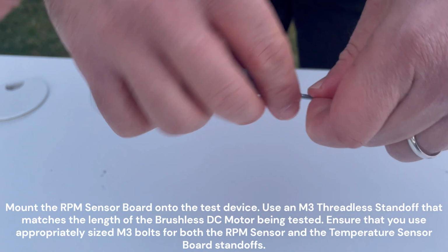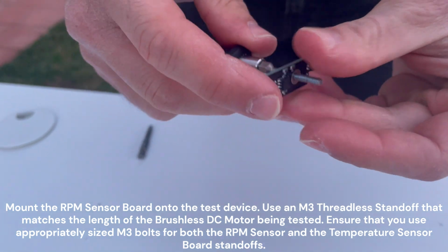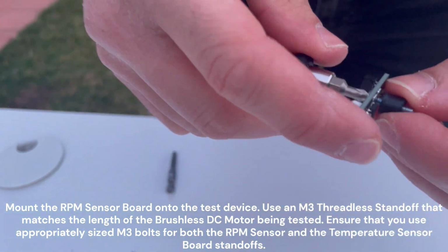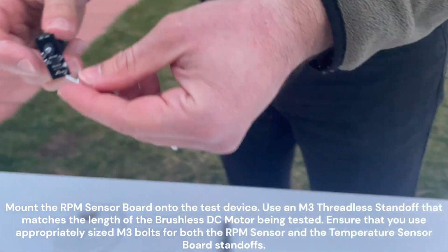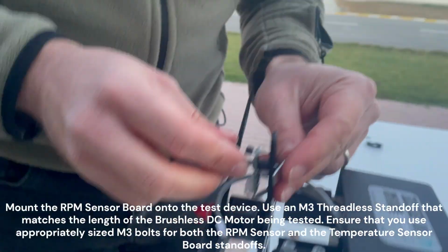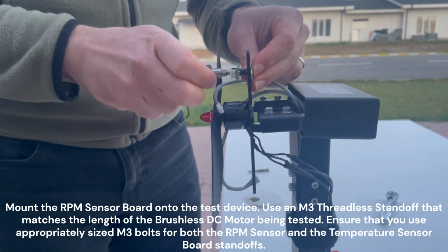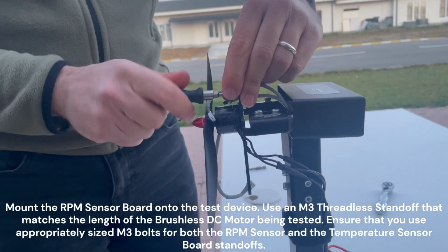Mount the RPM sensor board onto the test device. Use an M3 threadless standoff that matches the length of the brushless DC motor being tested. Ensure that you use appropriately sized M3 bolts for both the RPM sensor and the temperature sensor board standoffs.